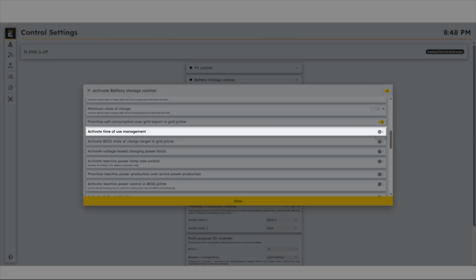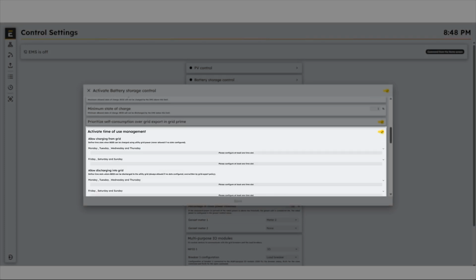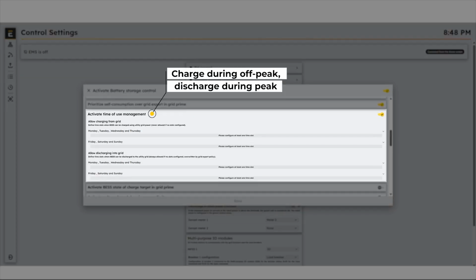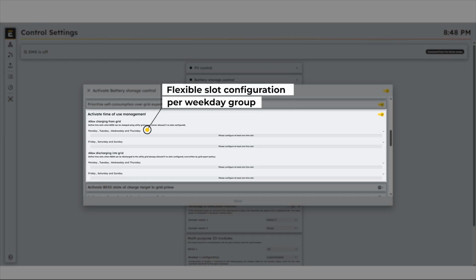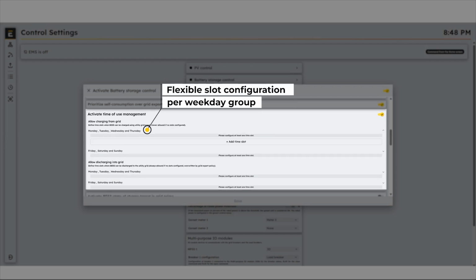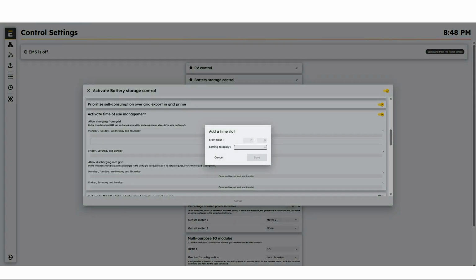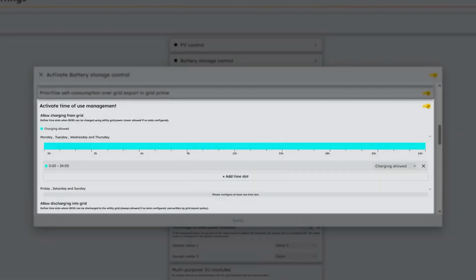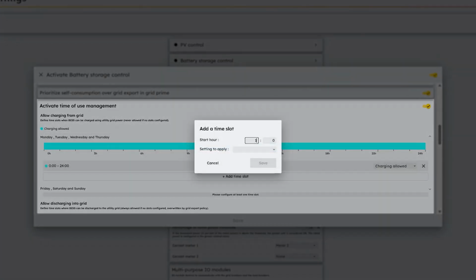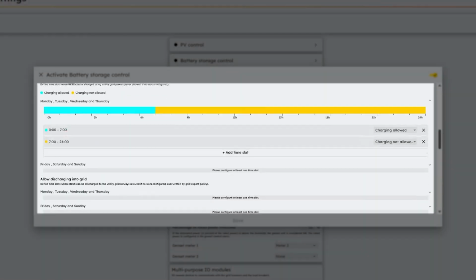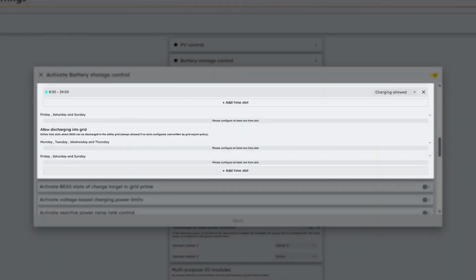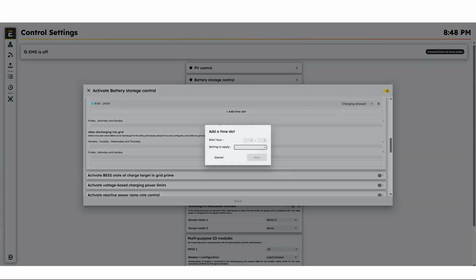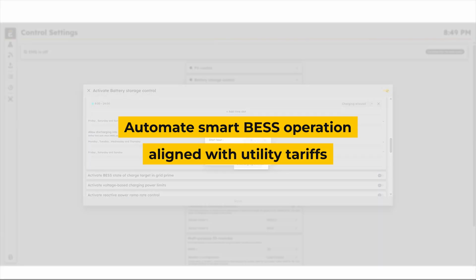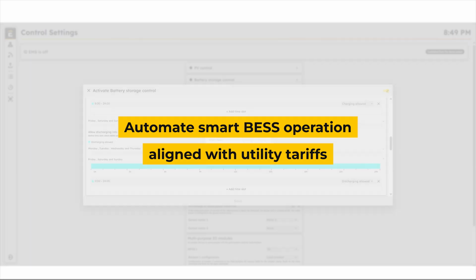Time of use management allows you to plan when the battery can charge from or discharge to the grid. You can define specific time slots for each day group, for example, charging at night during low tariffs and discharging during expensive peak hours. Even when charging from or discharging to the grid is not allowed, the BESS can still charge from PV production or supply the site load. This function helps optimize your site's energy cost while aligning BESS operation with local utility pricing policies.